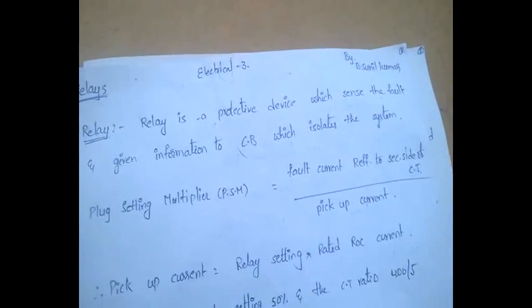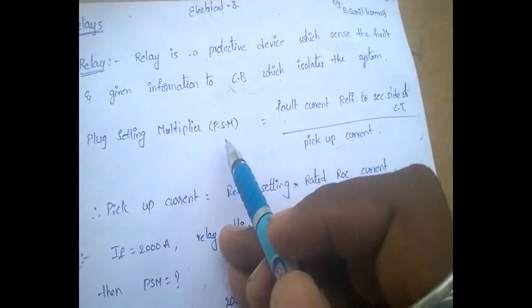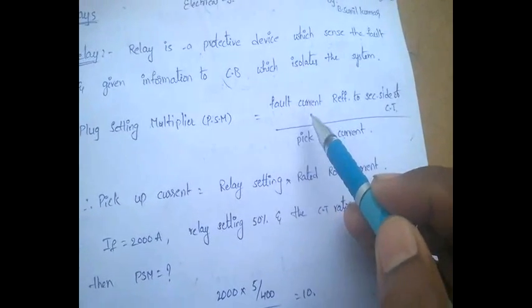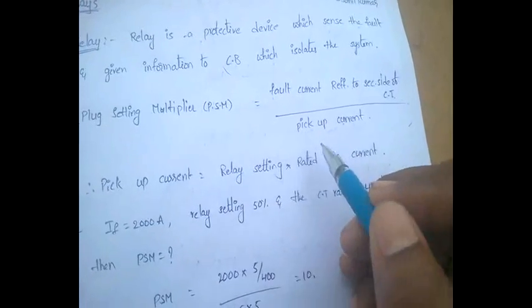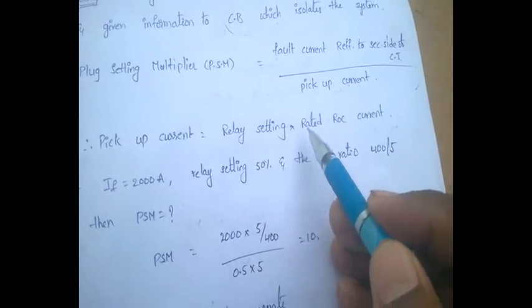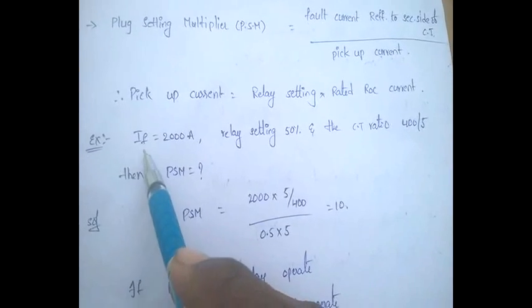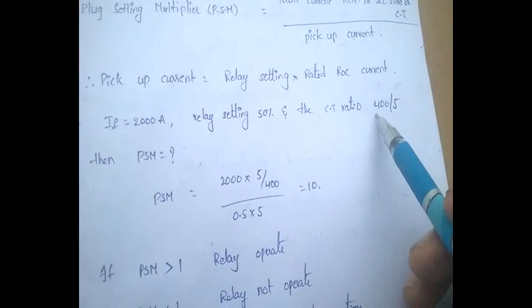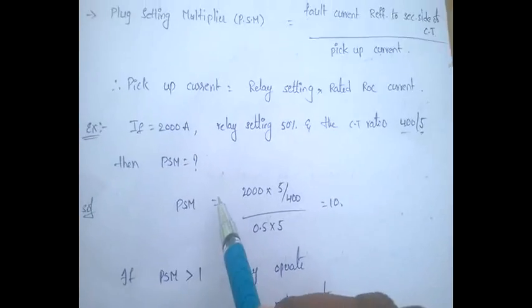In relays, a very important concept for problems is the Plug Setting Multiplier (PSM). PSM equals fault current referred to the secondary side of the current transformer (CT), divided by pickup current. Pickup current equals relay setting multiplied by rated secondary current. For example, if fault current If = 2000 amps, relay setting is 50%, and CT ratio is 400/5 (primary 400A, secondary 5A).